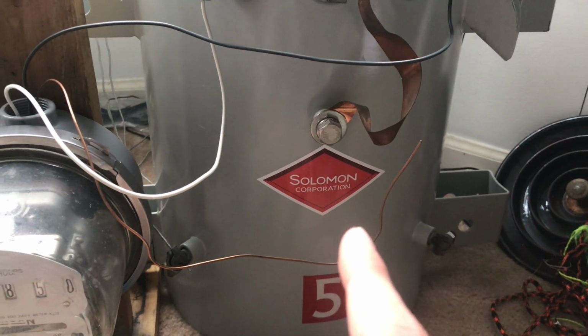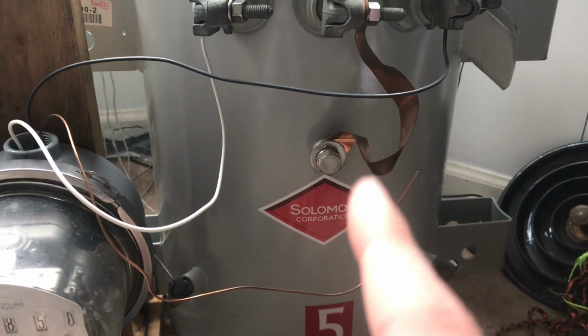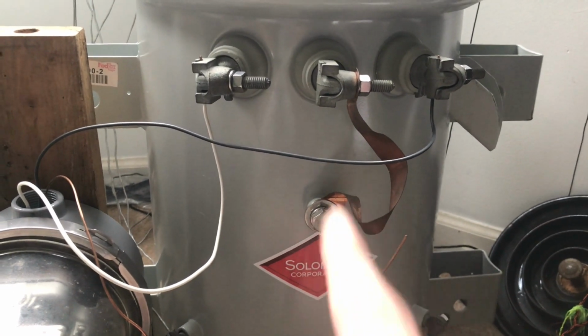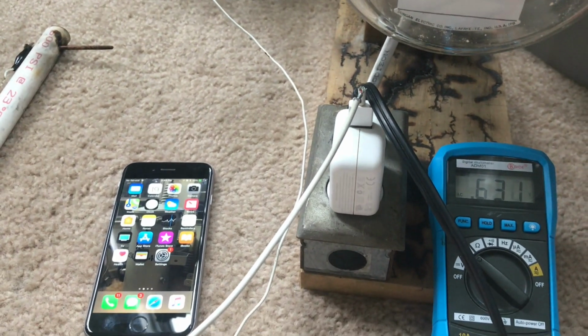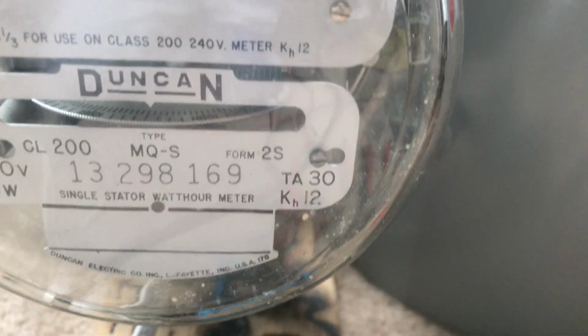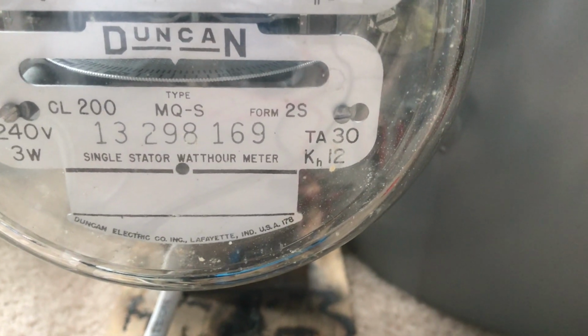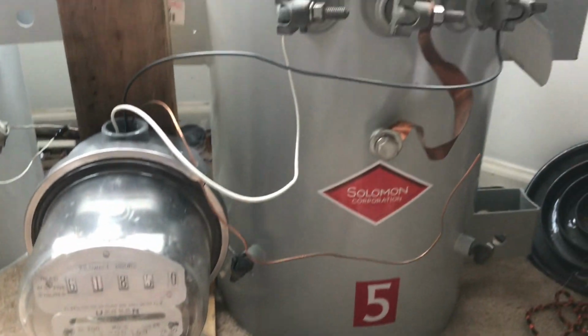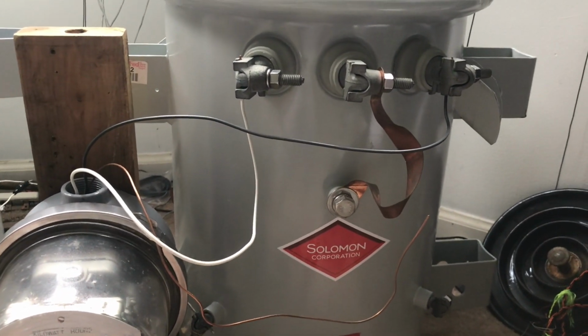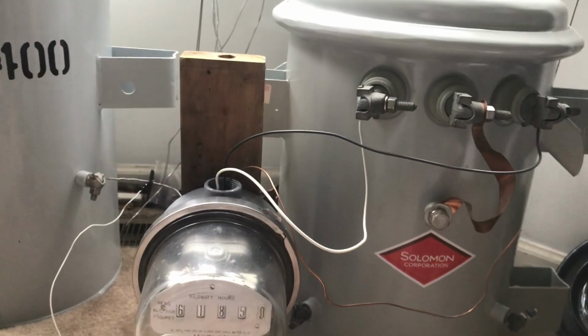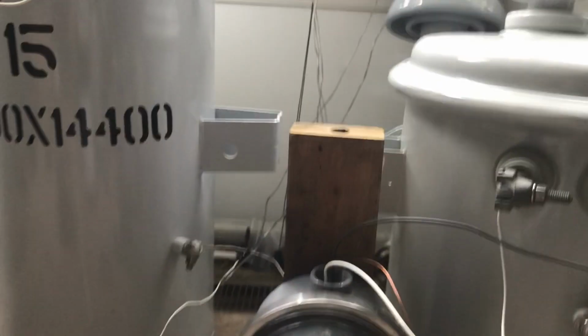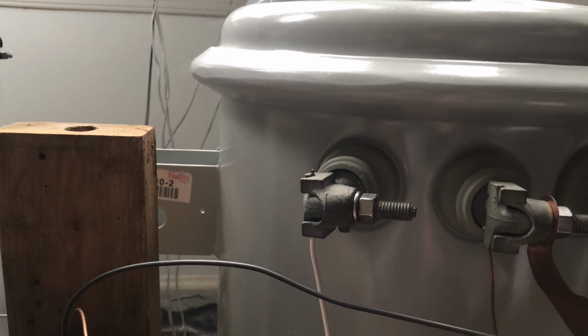Without the neutral conductor, which is there and live now, there is no way for the excess current that the space heater will use to get back into the transformer. So the iPhone is limiting the circuit to the amount of power that it can draw. And as you can see, the meter is spinning very slowly because it has just the load of the iPhone and space heater on it. Now I'm not going to reconnect this while it's live, so I will disconnect the system and then put the neutral back.